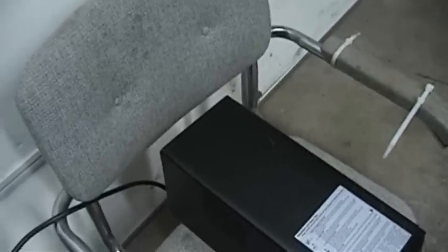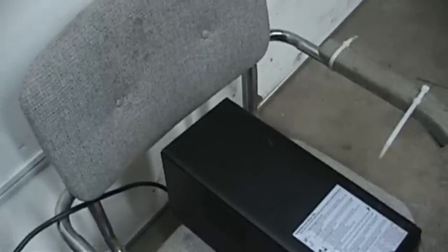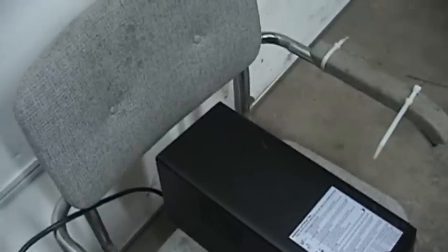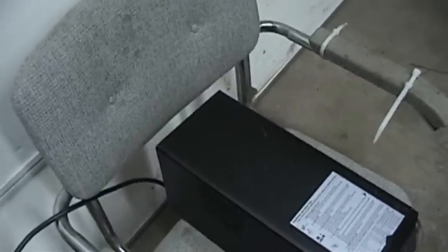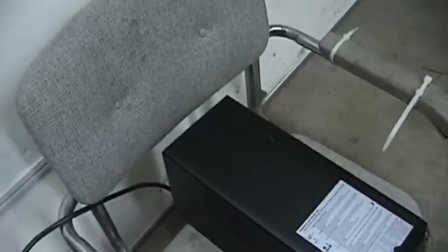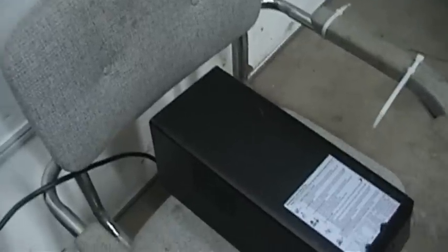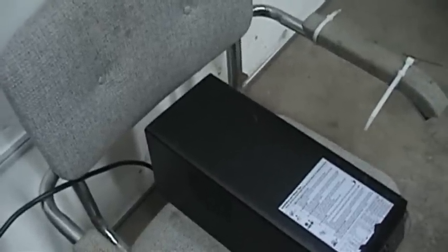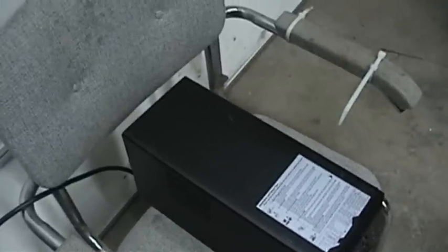I was once responsible for an APC Smart UPS 2200 that was carrying an 80% load, and while it held that load and did an admirable job, even though it has fan-forced cooling and the fan was working, it started to smell like burning after a while. That's something I'd rather not push as hard on, so I figure it's better to keep these units at or around 50% of their capacity at best. That way you're not beating the absolute life out of the batteries, and you're also not abusing the inverter too horribly or potentially causing it to overheat.